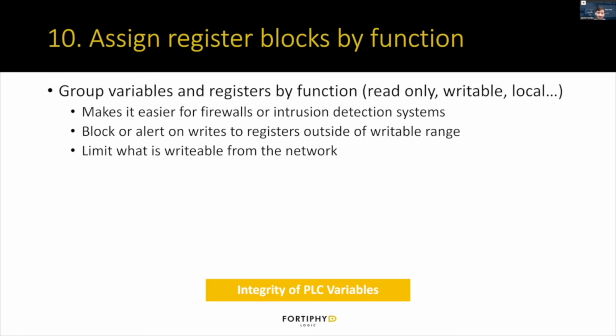Practice number 10 is assigning register blocks by function. The practices were written to be generic to any PLC, and so some apply more to legacy PLCs versus more modern PLCs for very specific scenarios. This one doesn't apply as much to CODESYS PLCs, but the idea here is that grouping variables and registers by function, whether they're read-only, writable, or local, makes it easier for firewalls or intrusion detection systems to either block writes or reads to different ranges of addresses or detect that, and just limit what is writable from the network.